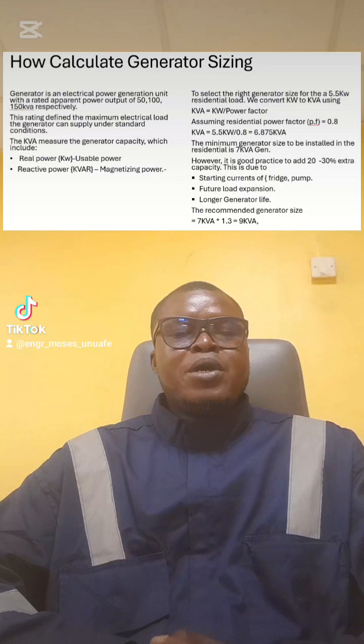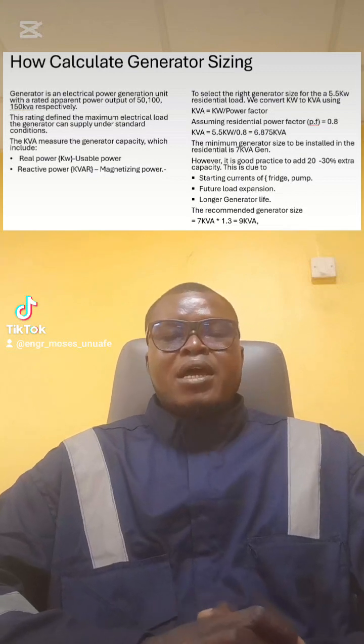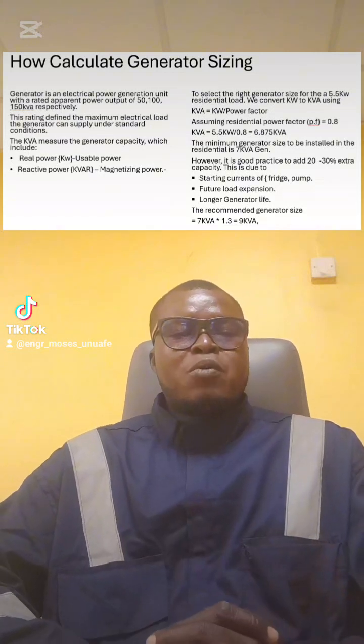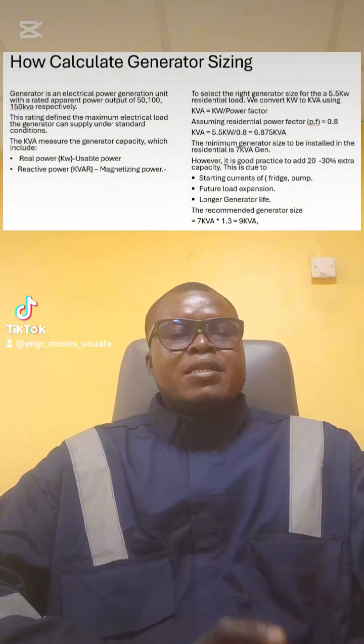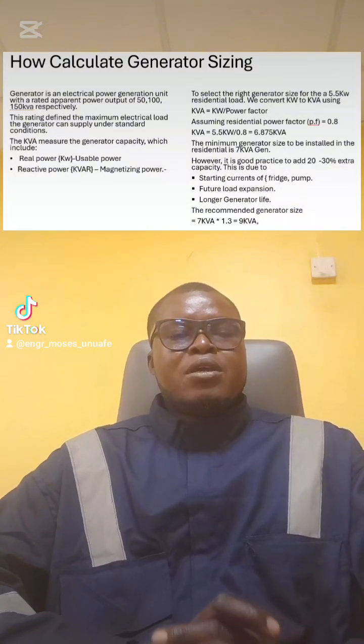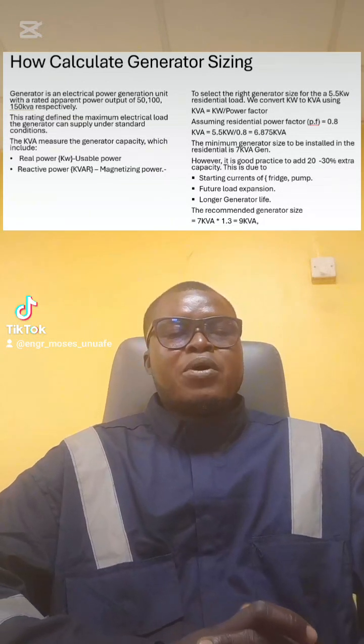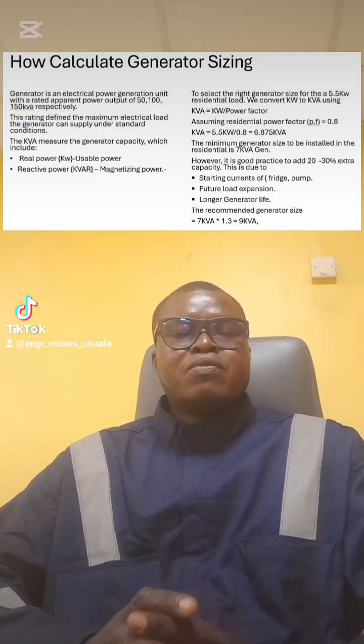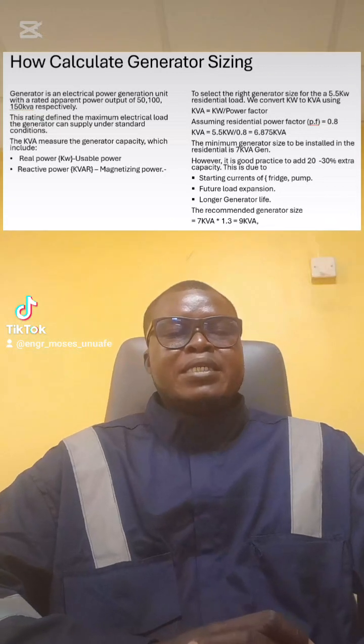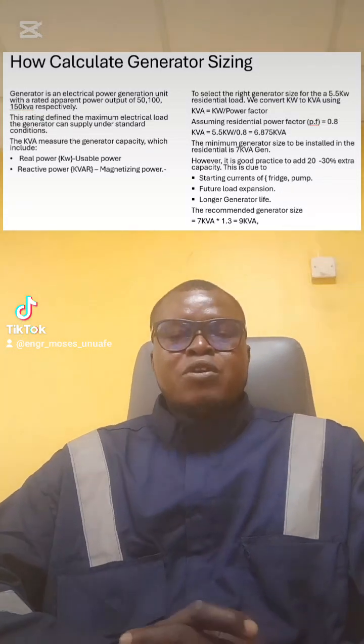Assuming that in our residential the power factor is 0.8, then our kVA is equal to 5.5 kilowatts divided by 0.8, which is going to give us 6.875 kVA. And approximately, the minimum generator size to install in that residential is a 7 kVA generator.